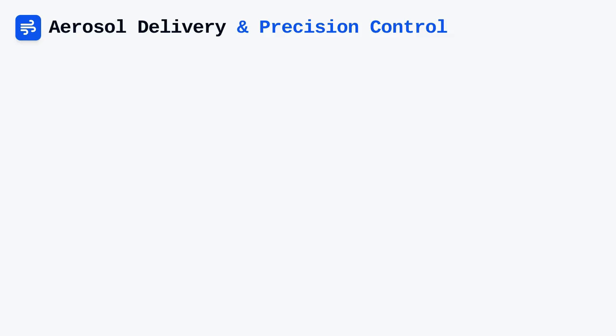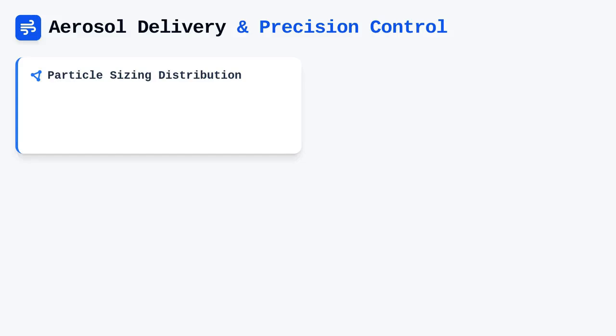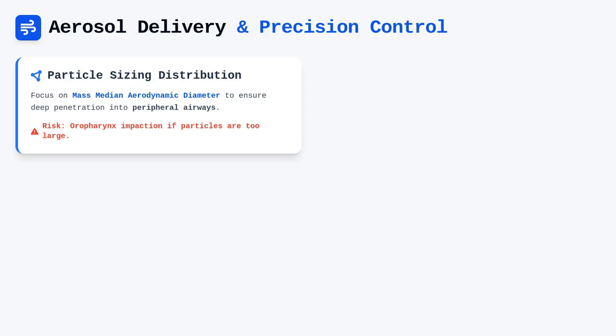Moving into aerosol delivery, we rely on nebulizers and automated dosimeters to standardize the administration of pharmacological agents, particularly during bronchial provocation challenges. The quality of a study here depends entirely on the aerosol particle sizing distribution, specifically the mass median aerodynamic diameter, which determines how deeply the particles penetrate into the peripheral airways. An improperly functioning nebulizer might produce particles that are too large, leading to significant impaction in the oropharynx rather than the target distal bronchi, thereby invalidating the provocation protocol.